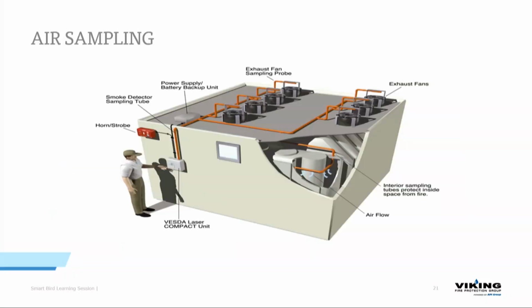We have our piping, perforated piping inside the unit, and it's also at each of the exhaust vents. So it can suck all that air out, travel its way back to this laser unit, which is checking for a specific chemical pattern or a specific chemical, and then it'll produce a horn and strobe alarm if it's starting to see that. There's not much.